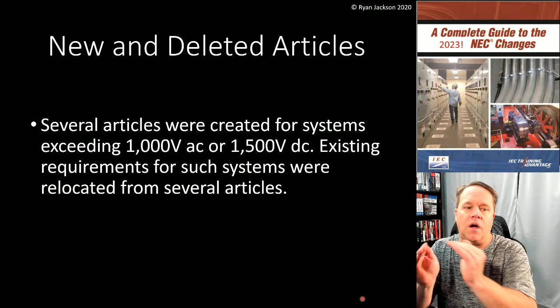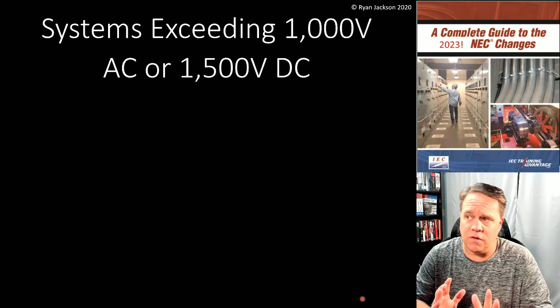So they went ahead and changed everything so you won't have Part 2 or Part 10 of Article 240 for over 1,000 volts anymore - that's gone. Part 8 of Article 230 that covered over 1,000 volts, that's gone too. They made their own articles for all the medium and higher voltage applications, which I think is really a good move.